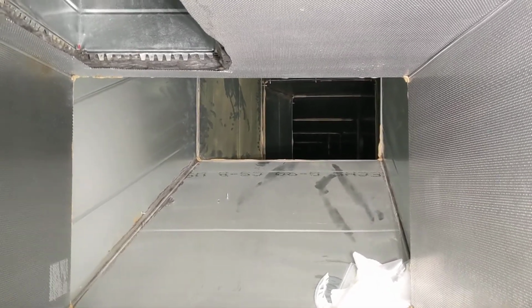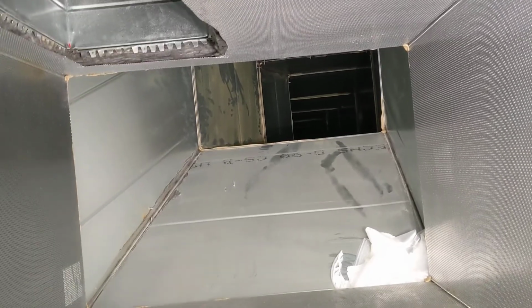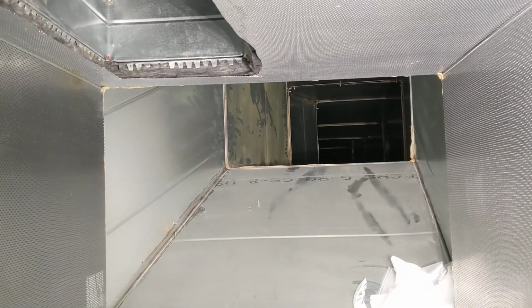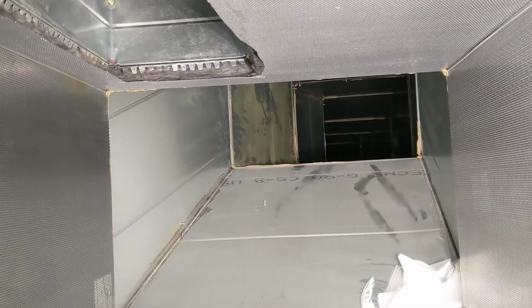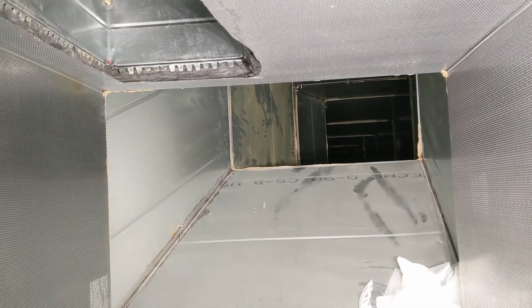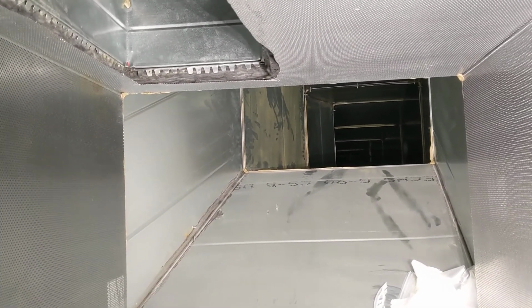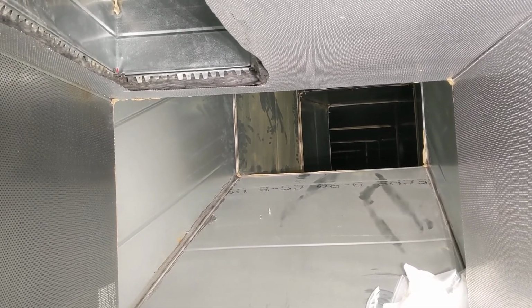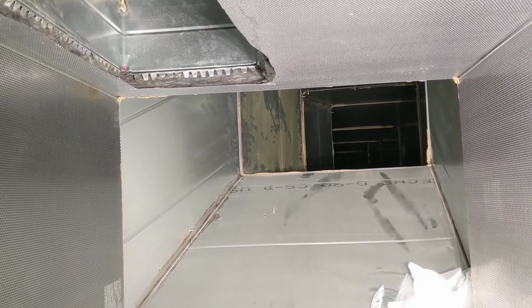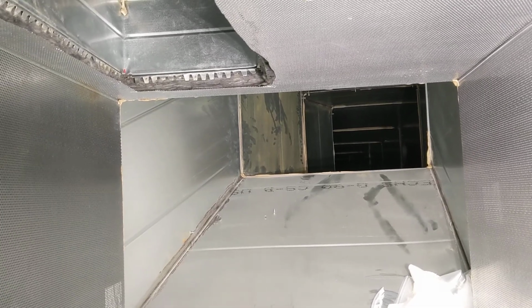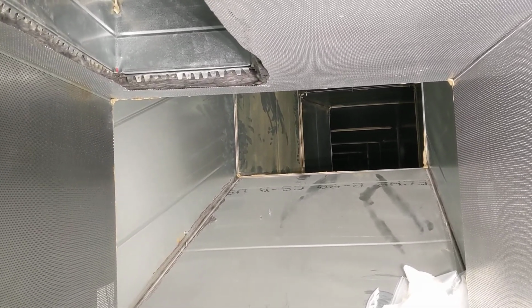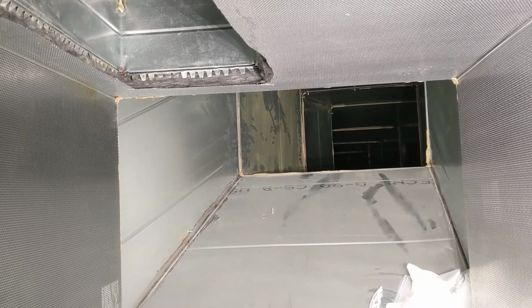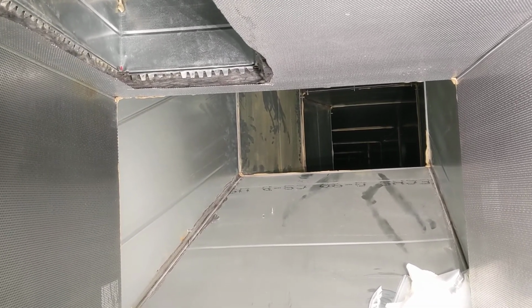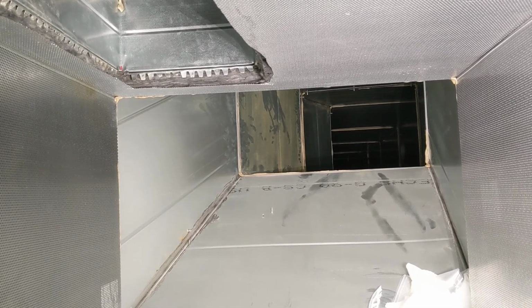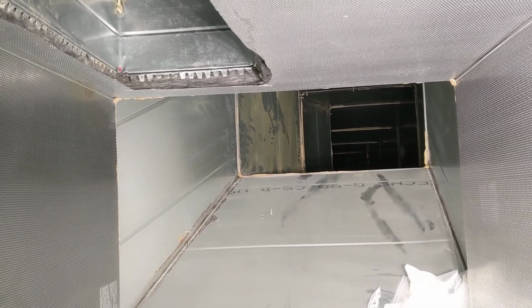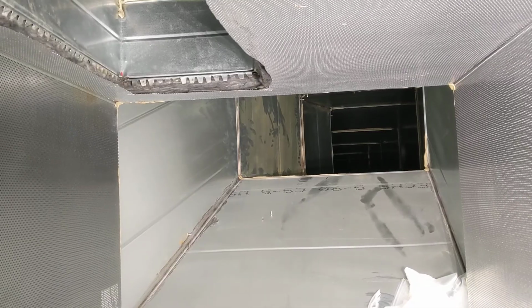There are two processes to clean ductwork depending on its size and setup. One is the whip system, the whipping method. In a nutshell, you have a HEPA collector on one end sucking the air through the ductwork, and a compressor with a whip system on the other end pushing compressed air through. So the HEPA collector pulls in one direction while the compressor and whip system push in that same direction to get all the dust and dirt out from start to finish.